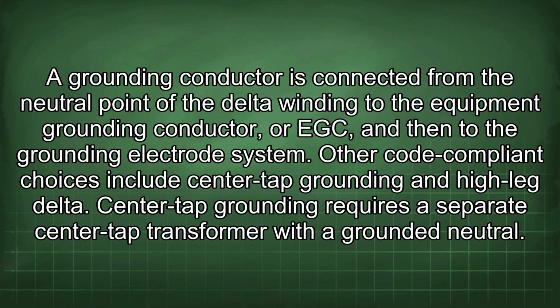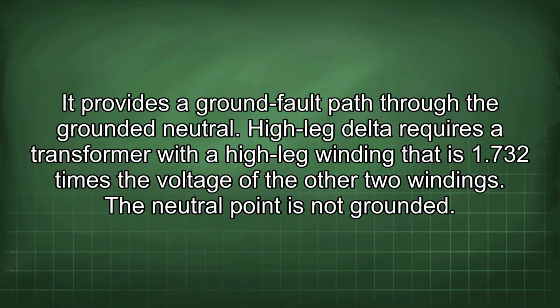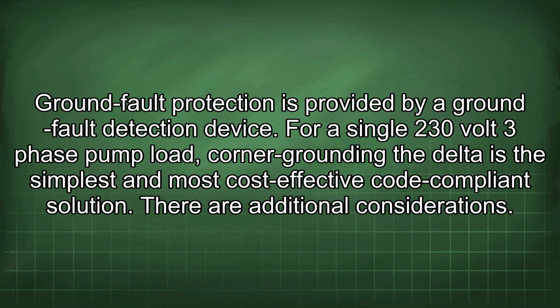Other code-compliant choices include center tap grounding and high leg delta. Center tap grounding requires a separate center tap transformer with a grounded neutral. It provides a ground fault path through the grounded neutral. High leg delta requires a transformer with a high leg winding that is 1.732 times the voltage of the other two windings. The neutral point is not grounded. Ground fault protection is provided by a ground fault detection device.